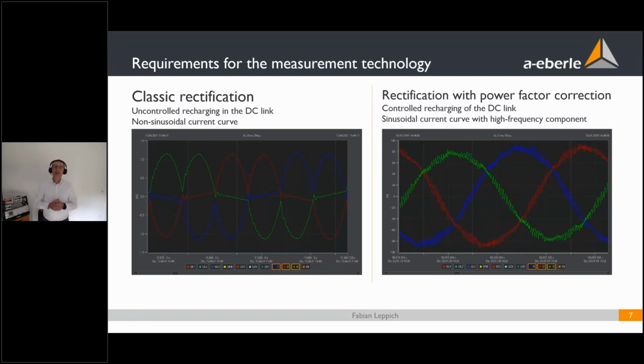With the new technology which we bring inside the grid, we have a rectification with power factor correction. What does that mean? We have here not an uncontrolled recharging in the DC link, but a controlled recharging in the DC link. And this ends up into a sine wave of the current looking like that. We often have a ripple depending on the grid impedance where this consumer or this PV power plant is installed. So we always have a sinusoidal current curve with a high frequency component.